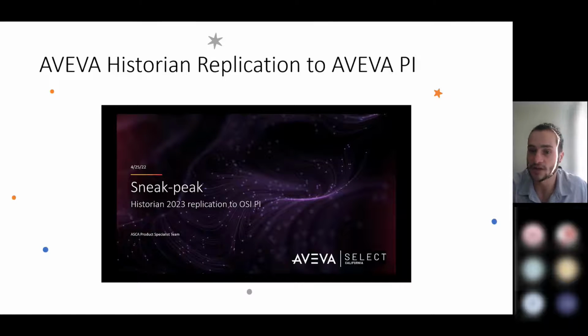So this actually strengthens your data security and fidelity and also allows you to segregate both systems and keep the users that are working off the business network out of your SCADA network. That way you can have a member of your organization use PI Vision or the PI DataLink client tool to visualize the data on their enterprise network.